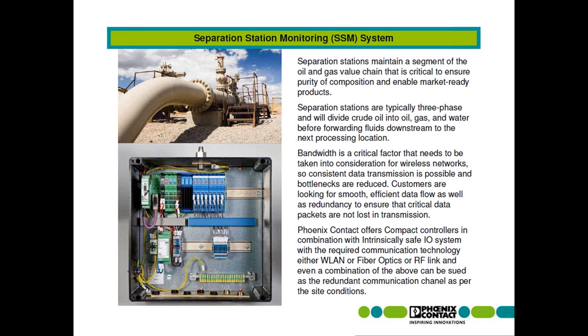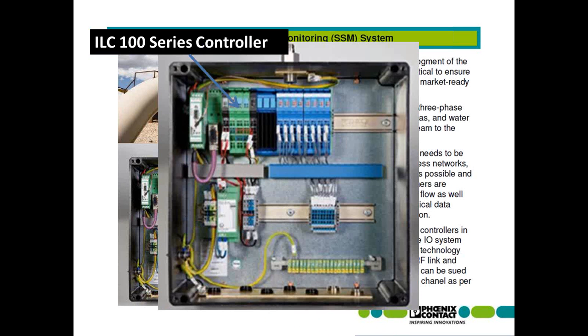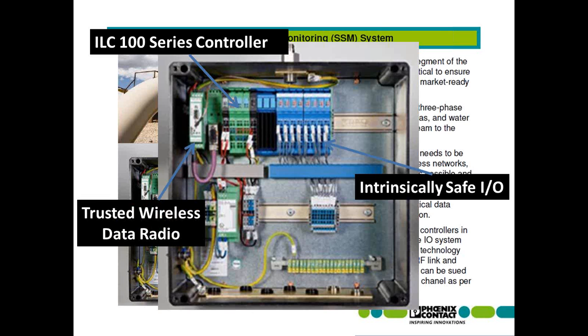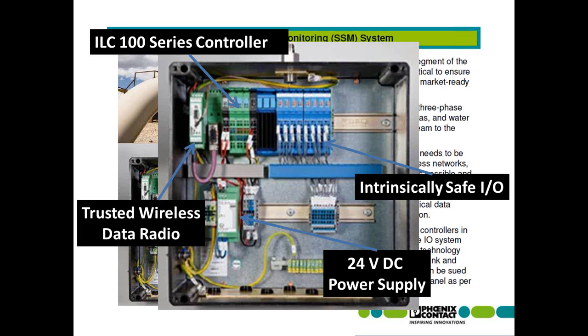So the unit we offer basically uses an ILC 100 series controller and can help manage and communicate the alarm conditions and communicate with the RTU through a data radio. Again, also using intrinsic I/O in those environments that are configured for it, you can work around the Class 1 Div 1 type of installations.